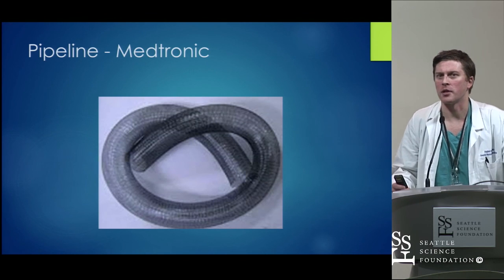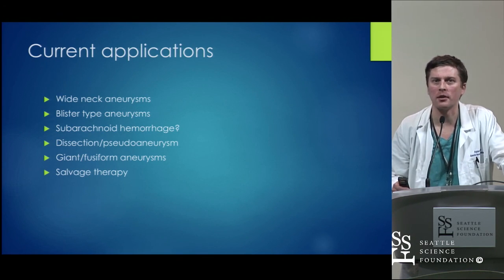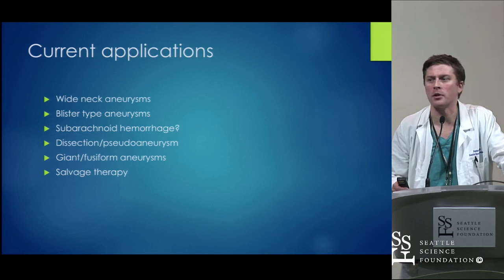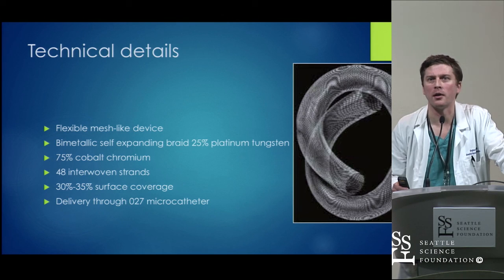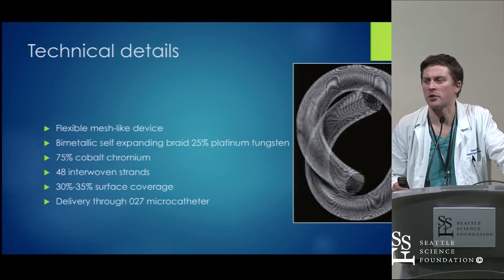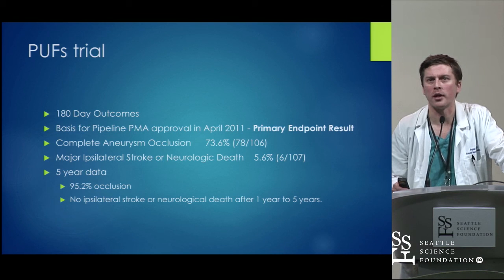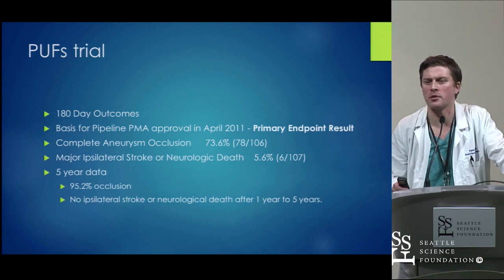The FDA-approved device in the United States is of course the Pipeline and Pipeline Flex. Originally approved for wide-necked aneurysms, off-label use has been widespread for blister-type aneurysms, subarachnoid hemorrhage, dissections, giant aneurysms, and increasingly for salvage of previously coiled or clipped aneurysms. It's a flexible mesh device — 75% cobalt-chromium, 48 strands — providing about 30–35% surface coverage. The PUFS trial was the main trial for FDA approval, with a complete aneurysm occlusion rate of close to 75% and a low stroke rate of 5.6%.